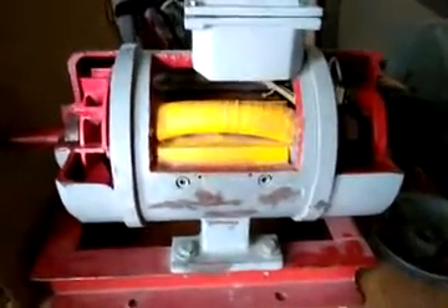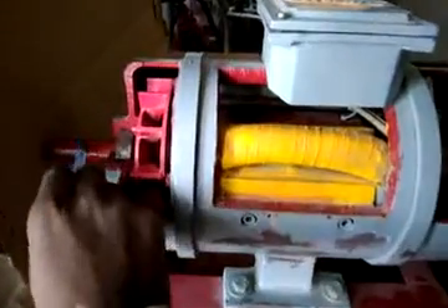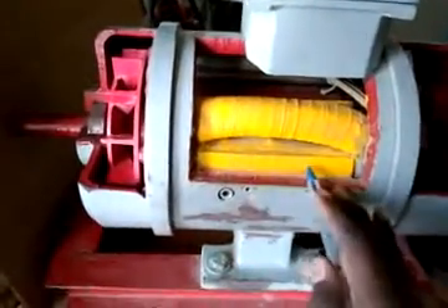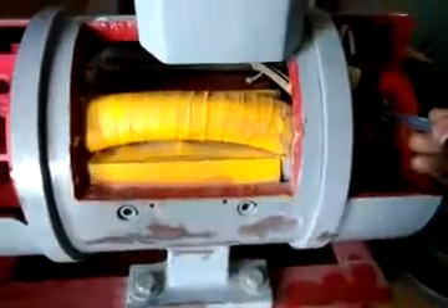This is the DC machine overhauling. Here we can observe in the shop there is a fan for cooling purposes. Next is the field winding with the field pole. Now coming to the commutator segment, which will convert AC to DC. You can now see here is the brush holder, and in between you can replace the brush. Commutator segments are made with hard-drawn copper.